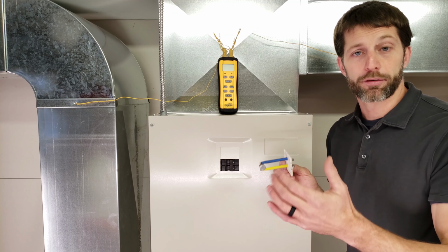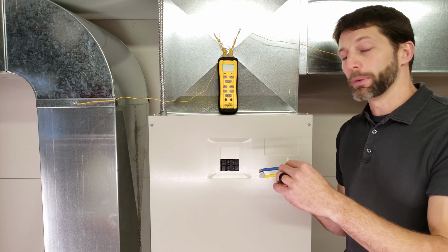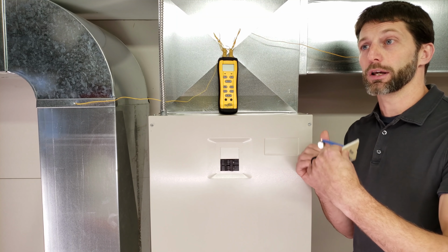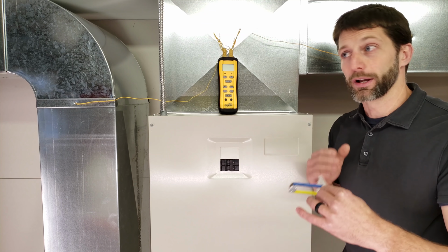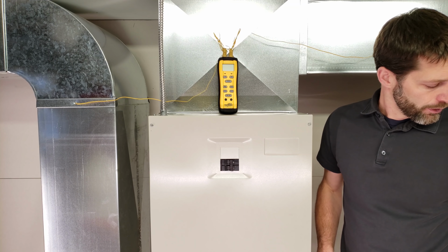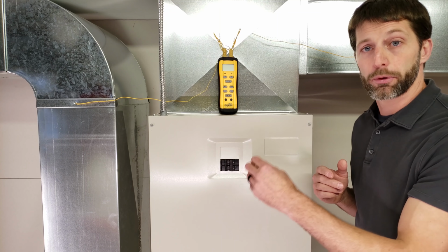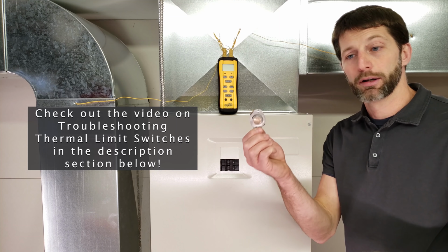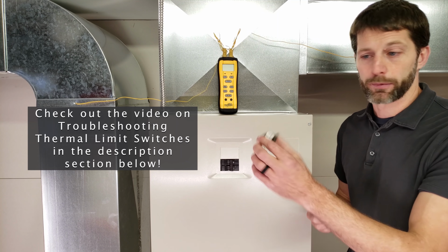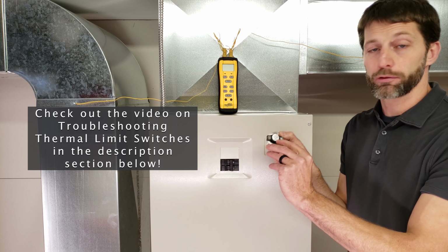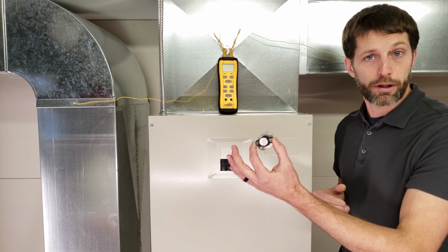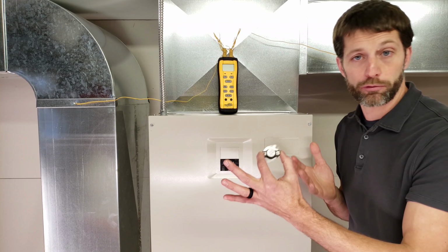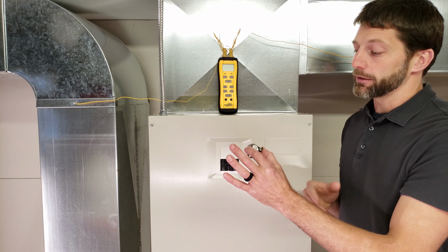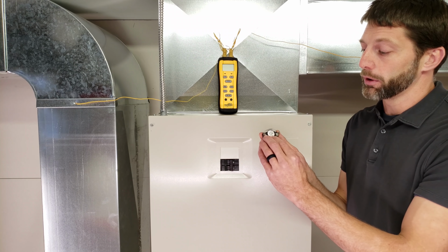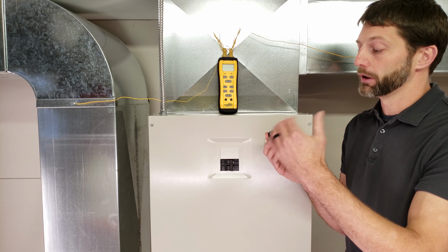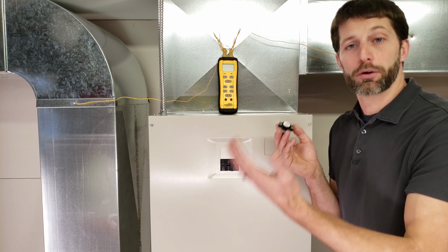Maybe your blower motor is bad, something is broken, or the capacitor is bad. So this is going to be a safety to keep your gas furnace safe, so it's not just continuing to overheat. On a furnace or an air handler with electric strip heating, you could have a sensor such as this right here, and once again there's your thermal limit, and in this case it's 145 minus 40. So this will be normally closed, and then it would open up if you got higher than 145 degrees, and it's not going to close back down again until you go 145 minus 40. So it's not going to close the electrical connections again until you get down to 105 degrees.